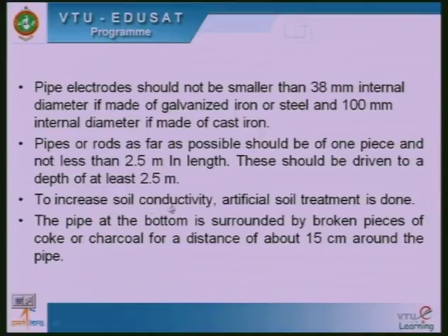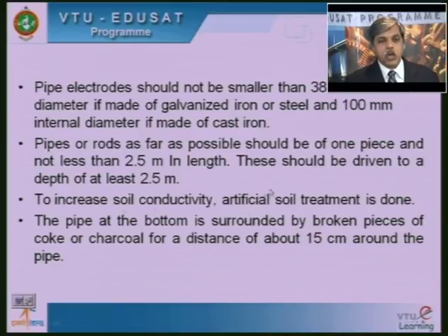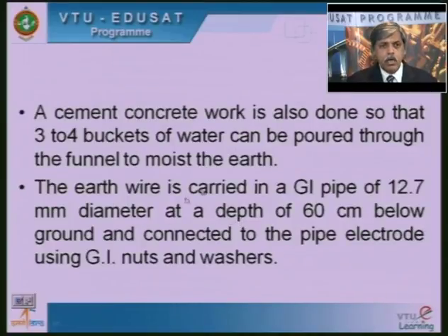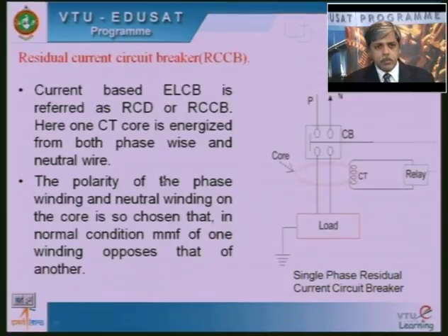Okay. To increase the soil conductivity, I will be using artificial soil treatment, that is putting charcoal and salt, okay, filling the pit with charcoal and salt, in alternate layers. The pipe at the bottom is surrounded by broken pieces of coke and charcoal for a distance of 15 centimeters around the pipe, okay. So this is what we call artificial soil treatment. And again I will be doing a cement concrete work at the top. So I will fix a funnel there through a filter, and I will be pouring water, okay, to increase the moisture of the ground, okay. So the method is almost the same.